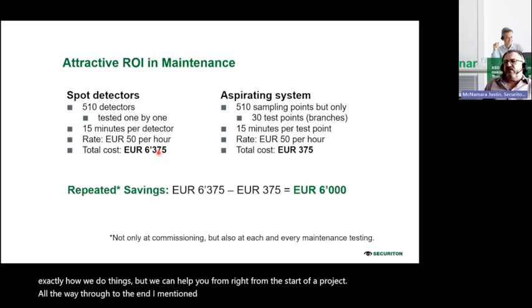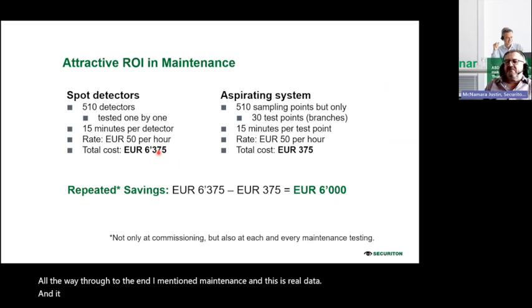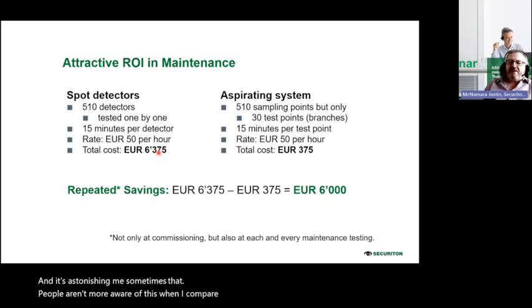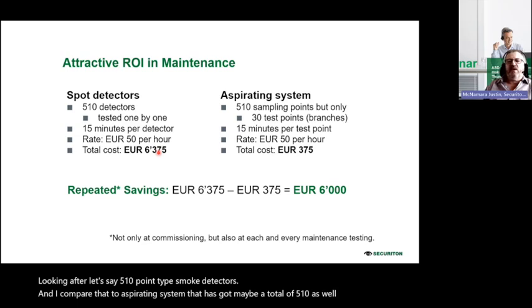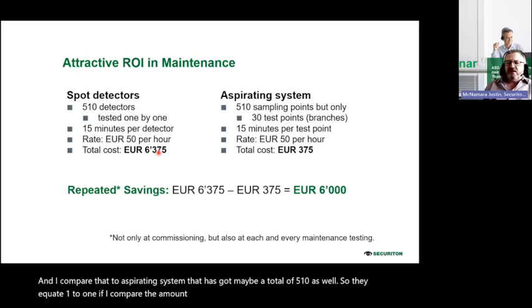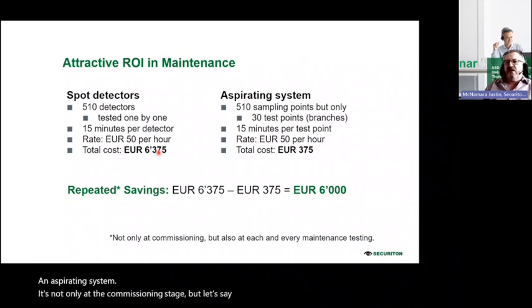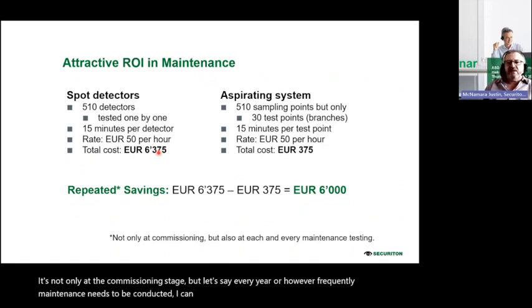I mentioned maintenance, and this is real data that astonishes me sometimes. When I compare the maintenance involved in looking after, say, 510 point-type smoke detectors to an aspirating system with a total of 510 as well, so they equate one to one, the amount of labor involved is unbelievable. Time is expensive, and using an aspirating system can save massive amounts of time and money, not only at commissioning but every year maintenance is conducted.